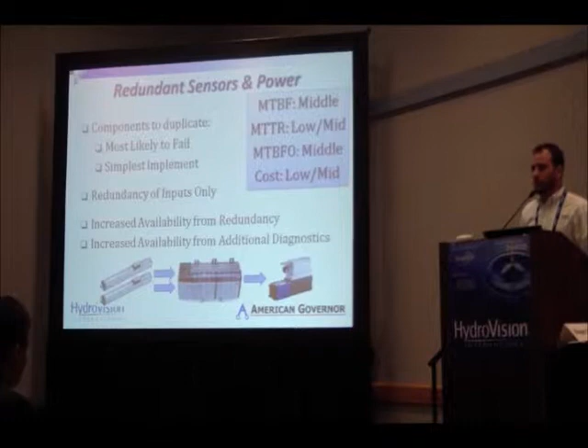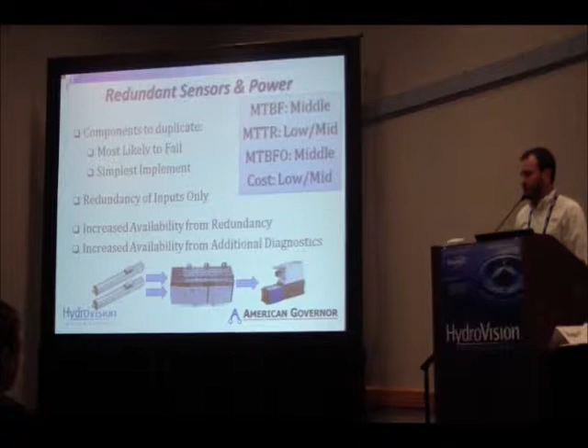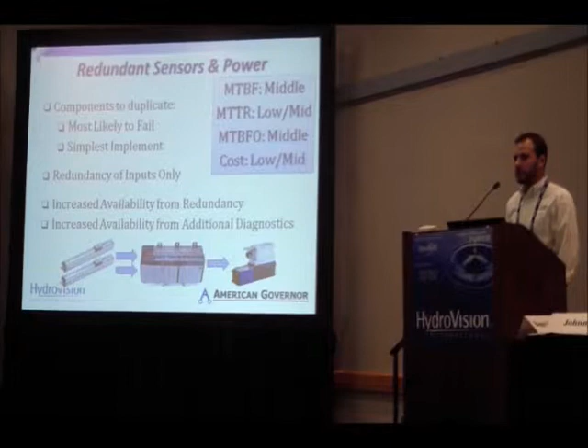So, if you want to increase your availability more than a simplex system, it's the next logical step. You want to duplicate the components that are most likely to fail, and the components that are easiest to duplicate. And that's typically your input signals and your power sources. Your power sources, because as most of you know, power sources are the most likely to fail.